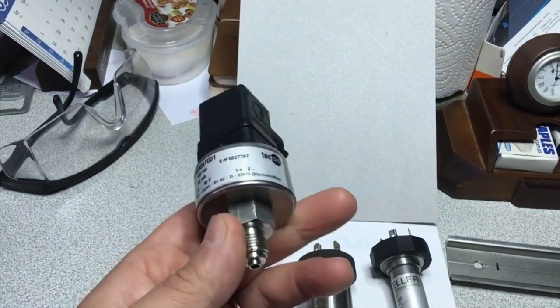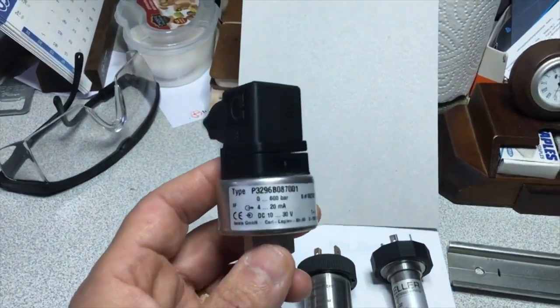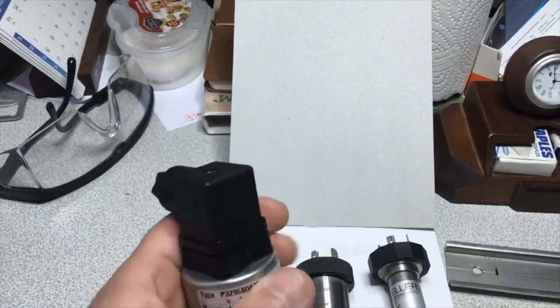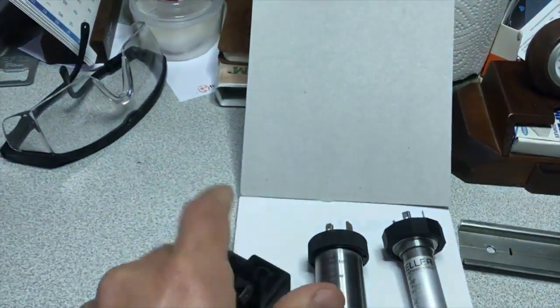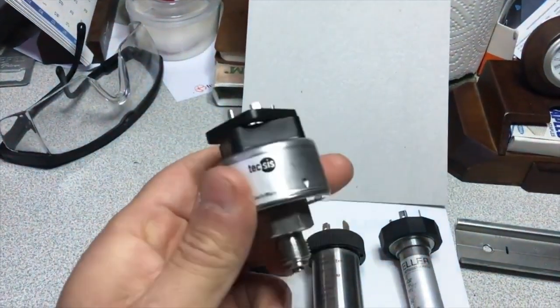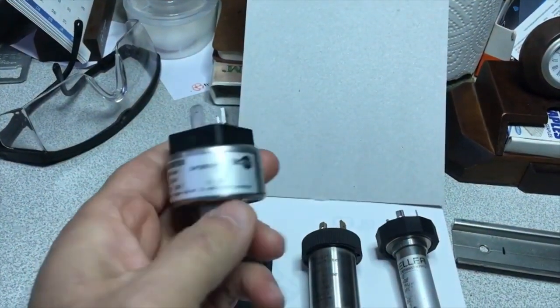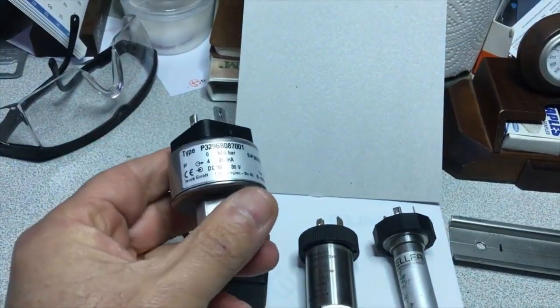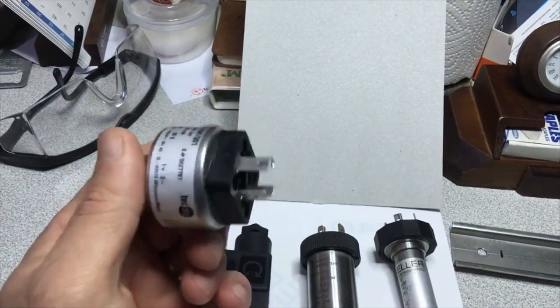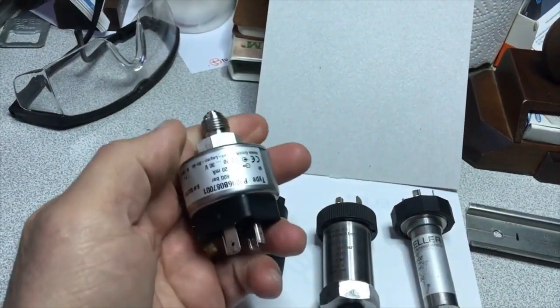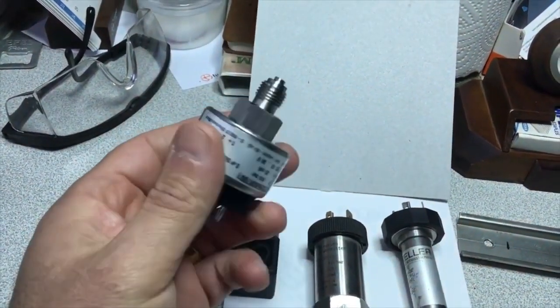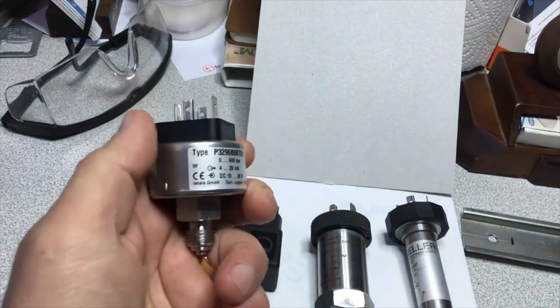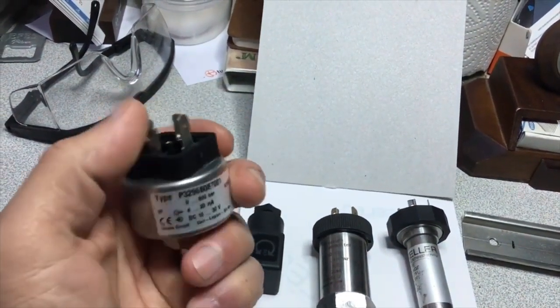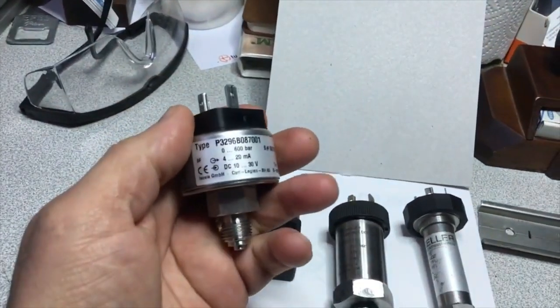The meaning of the output current is that when the pressure applied to our sensor is 0 bar, we will be able to output 4 milliamperes, and when the system pressure reaches 600 bars, the sensor will give us 20 milliamps output. The same sensors are also available with 0-10 volt output and 0 to 20 milliamp output. However, the 4 to 20 milliampere sensors are the ones with which you can measure most reliably and most accurately. Let me try to explain it this way.